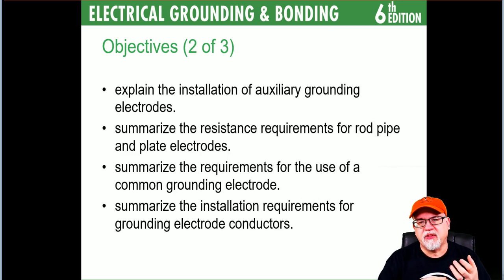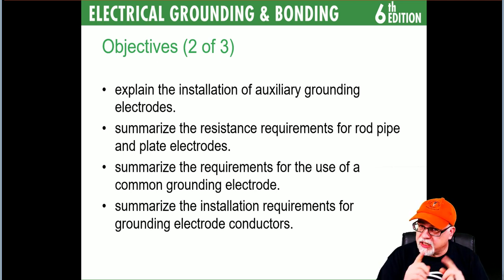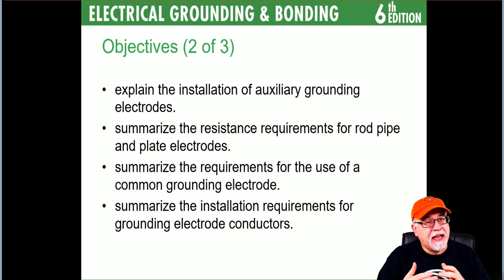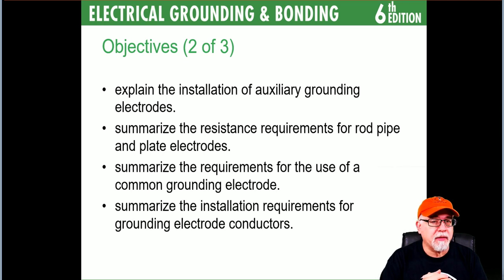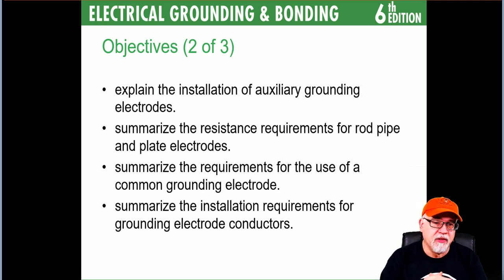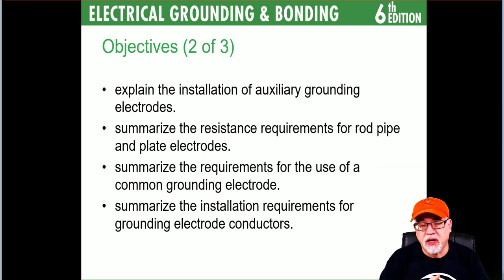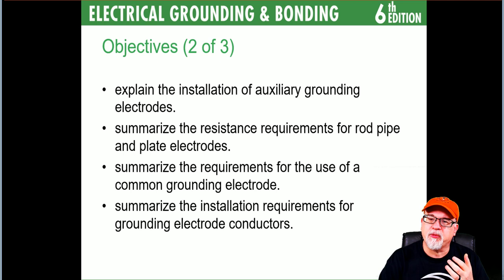You'll also learn about auxiliary grounding electrodes, which are different than supplemental. For example, a parking lot lamp pole might require an auxiliary grounding electrode by an engineer. An auxiliary is just optional — it doesn't have to meet all the normal rules within Article 250, but you get guidance from the engineer. You'll also learn to summarize the resistance requirements for rod, pipe, and plate type electrodes.